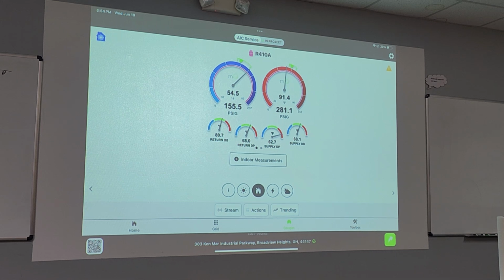Now the problem with doing that is we have algorithms in this to detect duct leakage. We know that your target low side pressure is driven very much off of your return temperature and humidity. If I were to take that probe off the unit and bring it in here where it's cooler, you would see that low side target pressure go down. So we have an algorithm that can detect if there's duct leakage. Based on the return air temperature, we know what the suction pressure should be. And say you put the return probe over the air grill in the living room, right? And so you're sucking back 72-degree air, but your suction pressure is high, it's probably going to trigger a fault saying check for duct leakage, because you could be sucking hot attic air in downstream of the return probe. So even though the probe's seeing 72-degree return air, the evaporator is seeing 85-degree return air.